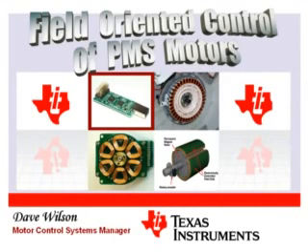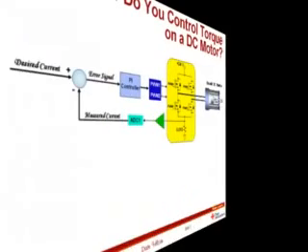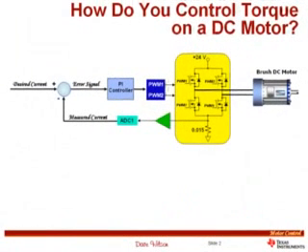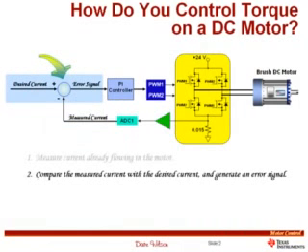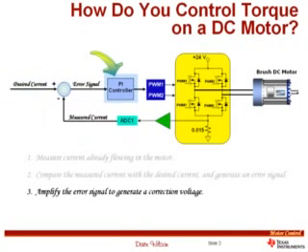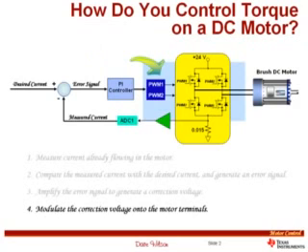To introduce the topic, let's first look at how torque is controlled in a DC machine. On any electrical machine, in order to control torque we must control the current. We divide the process into four distinct steps. Step one: measure the current already flowing in the motor — here shown via a shunt resistor feeding an A-to-D converter. Step two: compare the measured current with the desired current and generate an error signal. Step three: amplify the error signal to generate a correction voltage — if current is too low, increase voltage; if too high, decrease it. Step four: modulate the correction voltage onto the motor terminals.